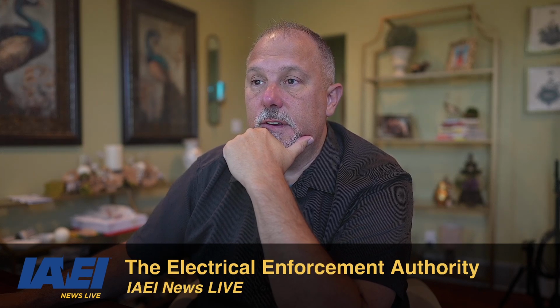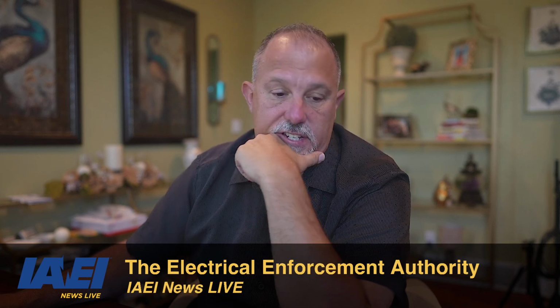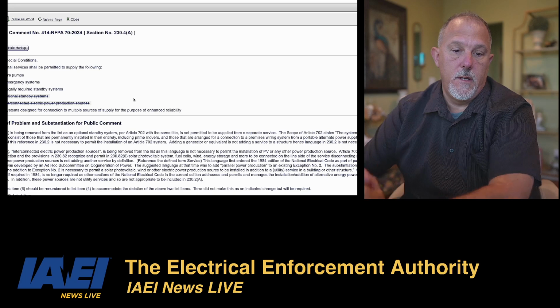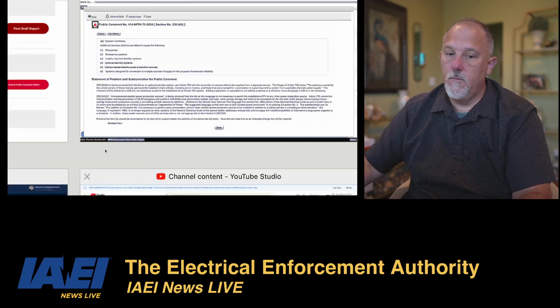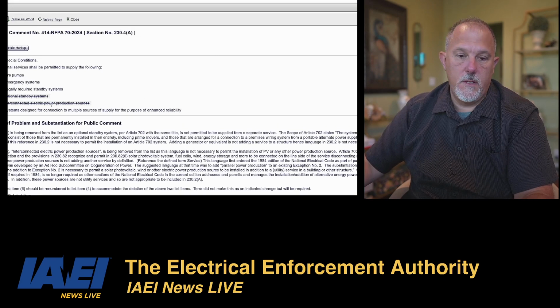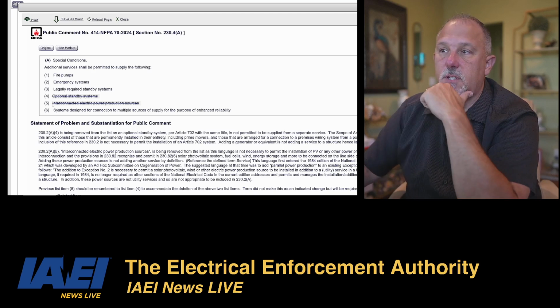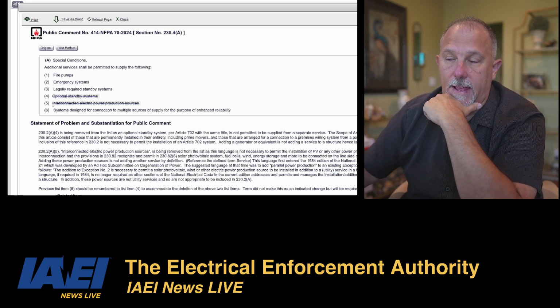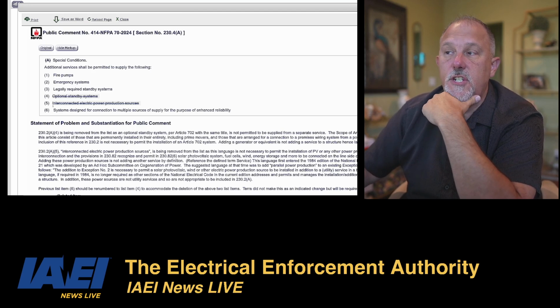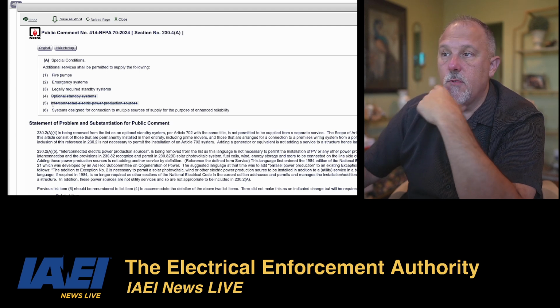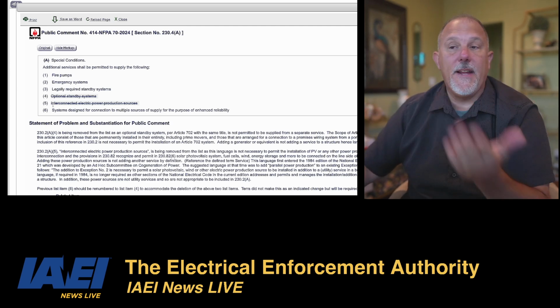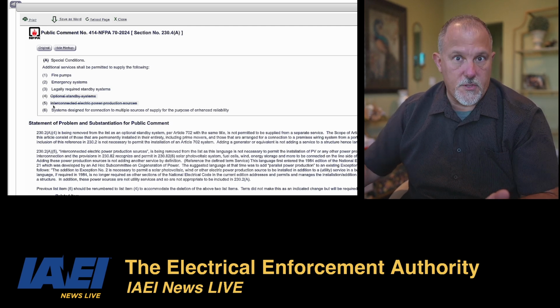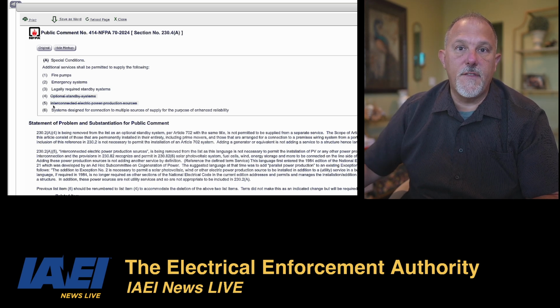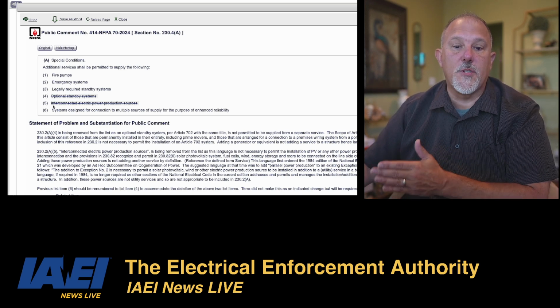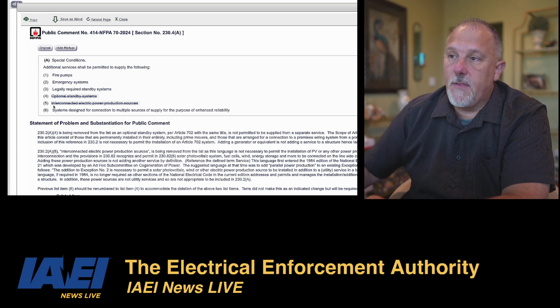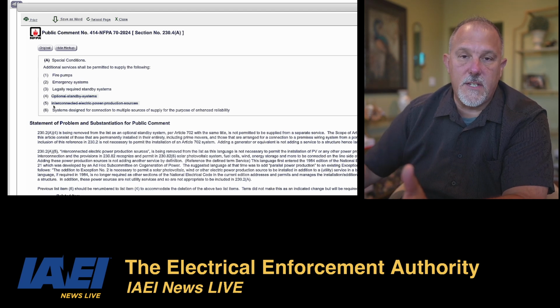I have this change here that I submitted, that deals with fire pumps. 230.4(A), special conditions. Additional services shall be permitted to supply the following. I'm removing optional standby systems, and that is because with optional standby systems, Article 702, you can't have a utility be one of your optional standby systems. So it didn't make sense to include that in the list.